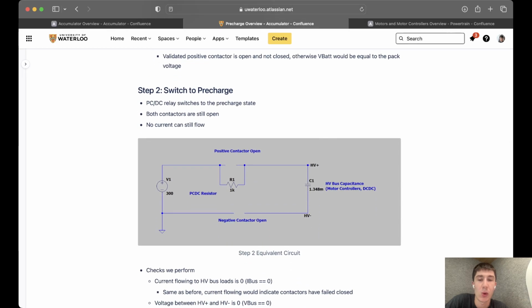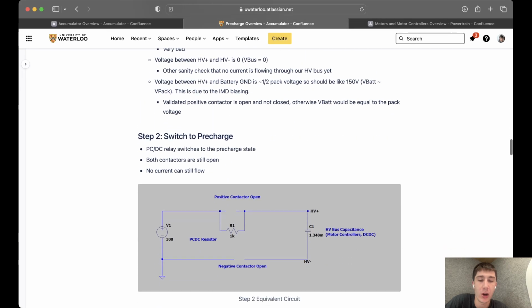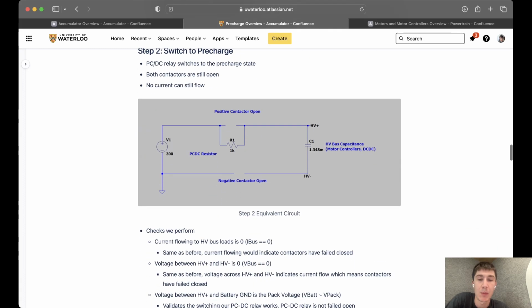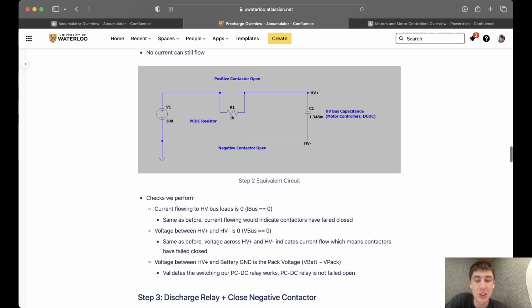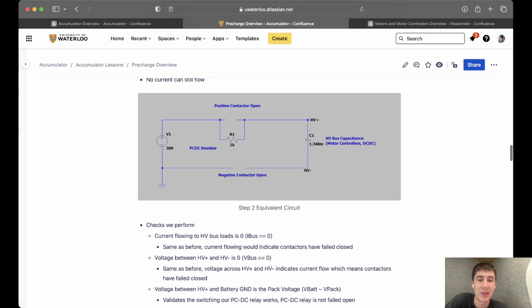The next step is we want to switch to precharge. So we move our PC-DC resistor from discharge mode into precharge mode. So we attach our resistor across our positive contactor. Our contactors are still open, but we just move the PC-DC relay to get it in that situation. Perform a bunch of checks here to make sure everything is good and our measurements are good. We have a bunch of ADCs at each point to run sanity checks and make sure the connections are proper.